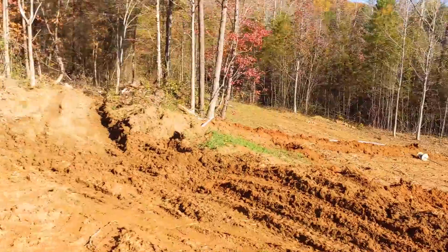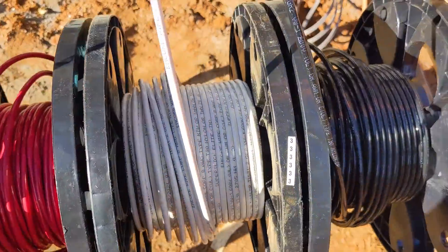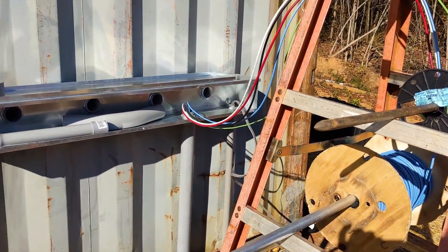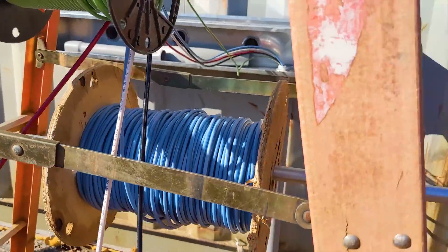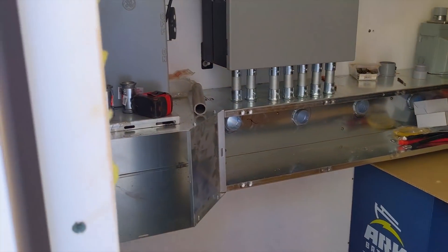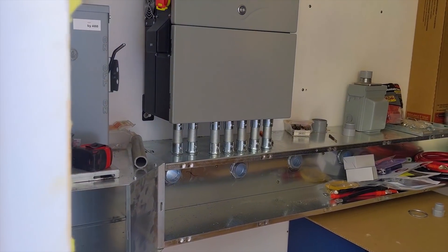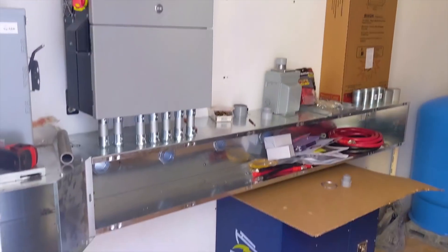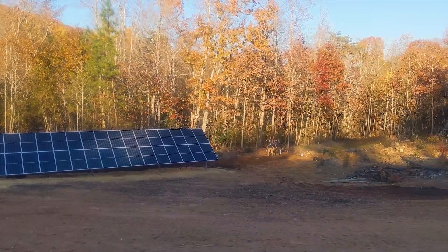Beginning of day three — we just pulled our number-eight wire. We could have used tens but had some long cutoffs from the last job, so this is great. It's our DC pull — four conductors and a ground. We'll make sure we have enough and bring that in through the wiring troughs, feed it up into the solar right there and get these batteries charging. The goal on this day is to get the batteries charging and do software updates, making sure everything works with the inverter while we work on the AC side.